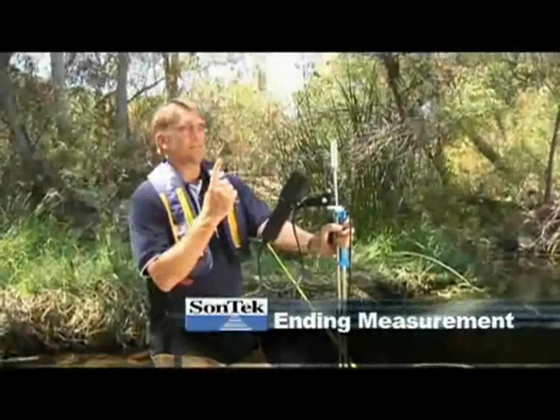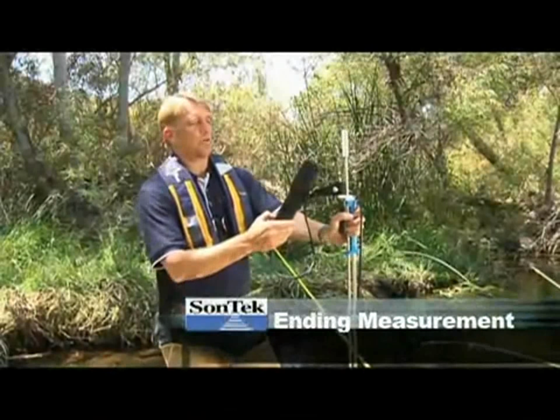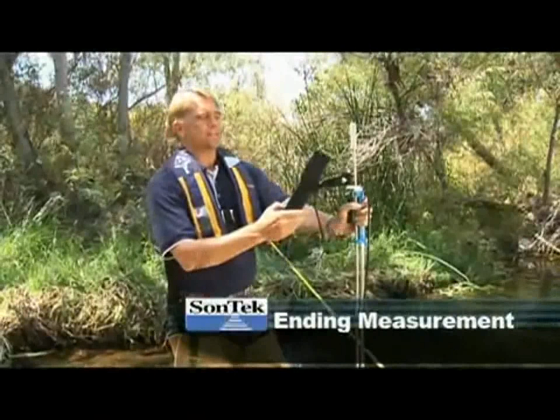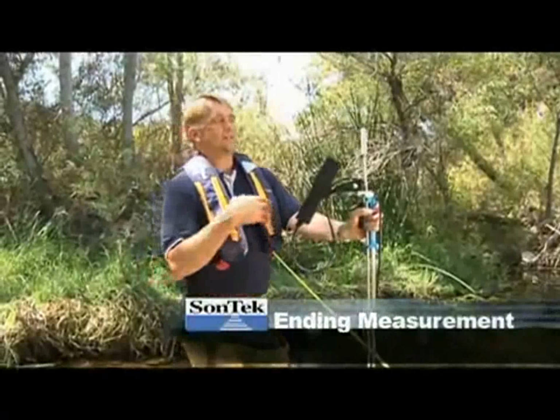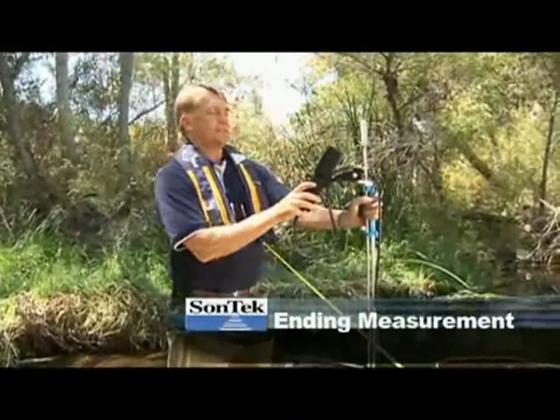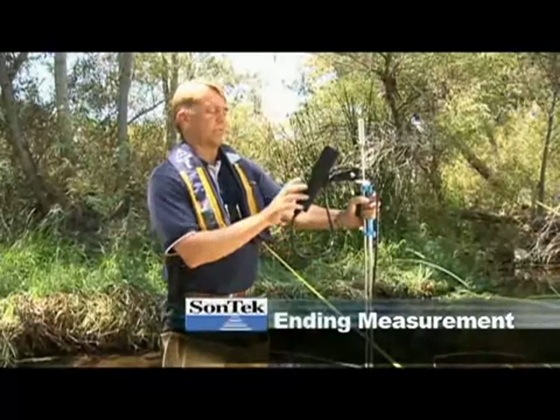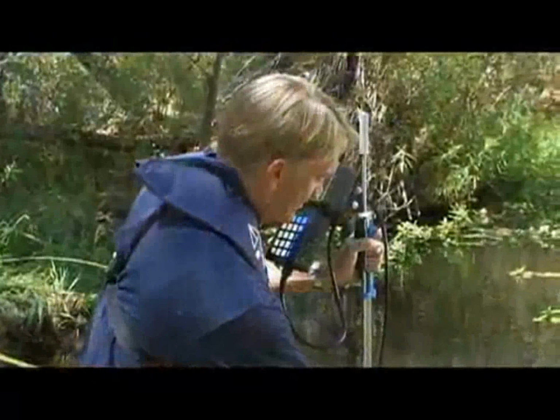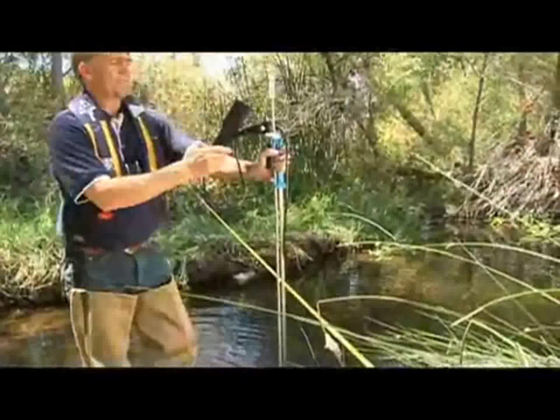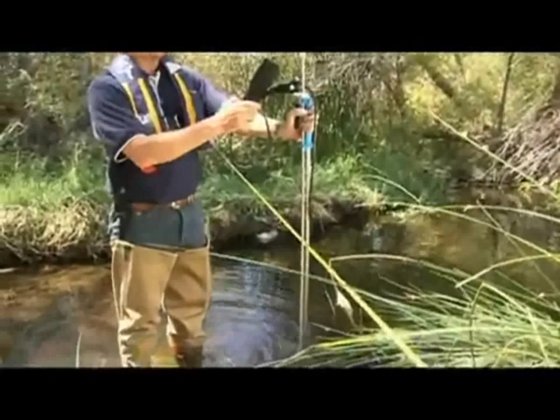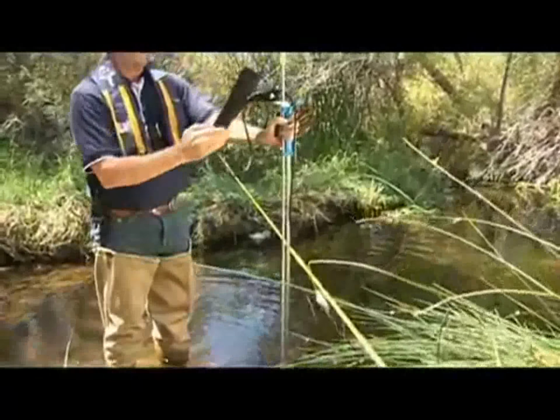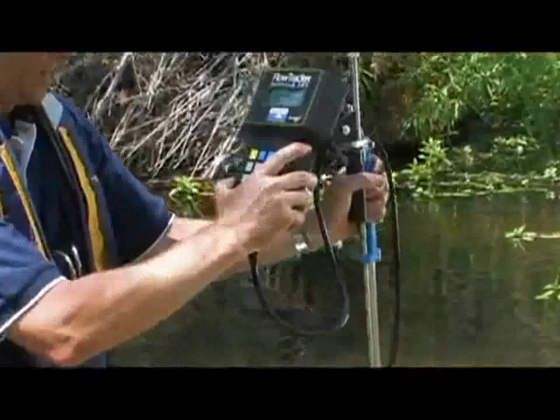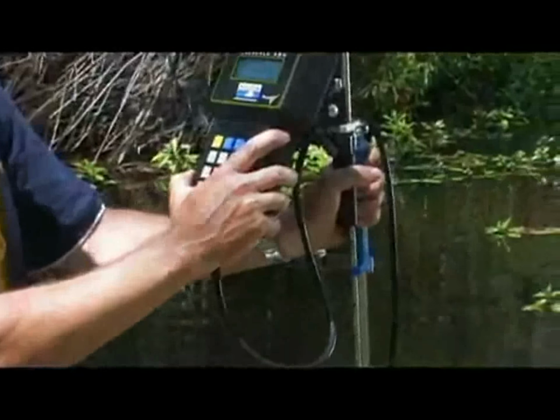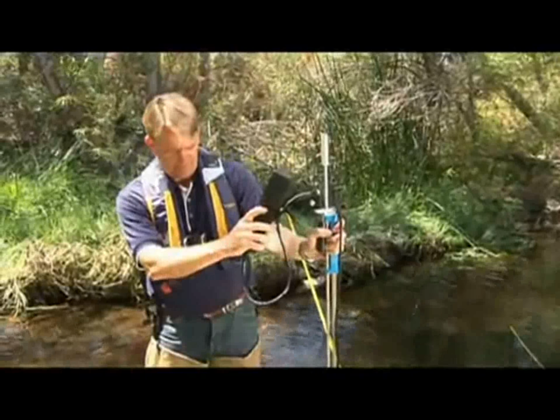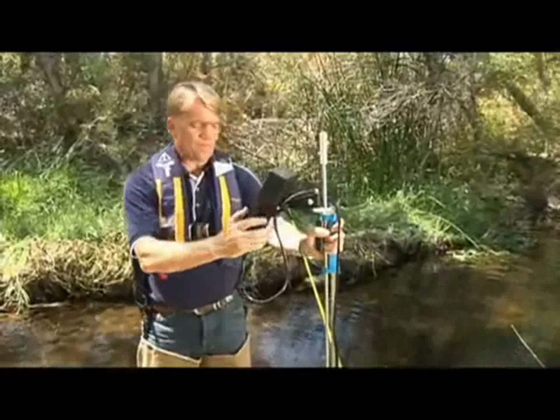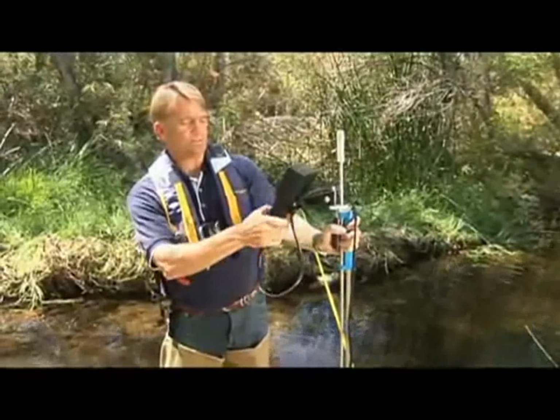It's going to ask me, are you sure? Basically, I'm going to have to press it twice. So I'm going to press end section again, and now it asks me to give the edge distance and the depth. The edge section is at 6.3, so I put the location of 6.3, and I'm going to measure the actual depth. Again, we have some depth here. .21.